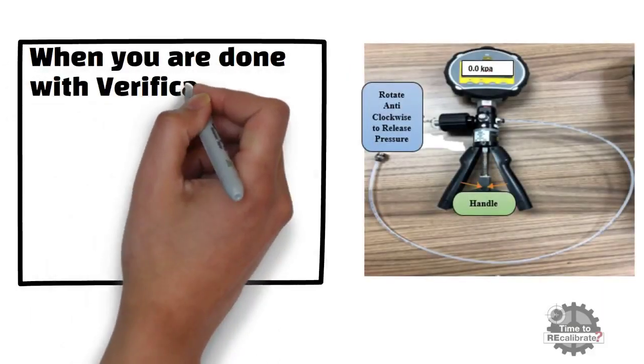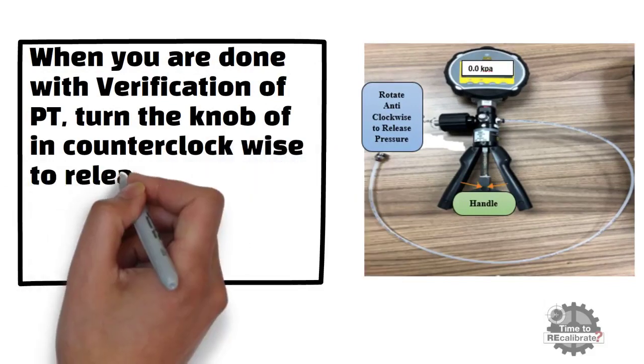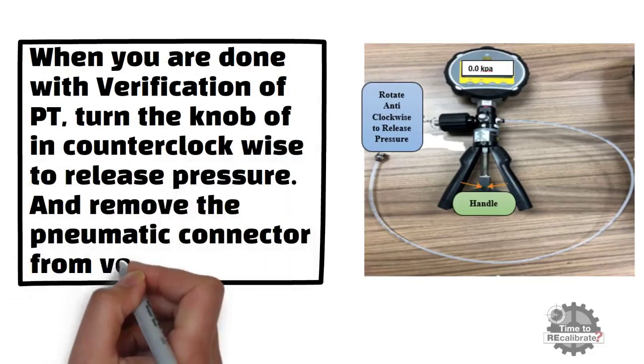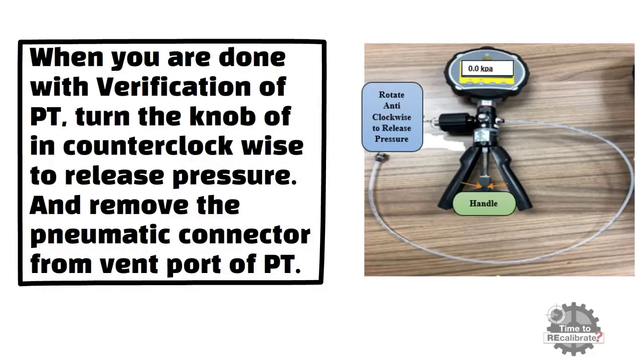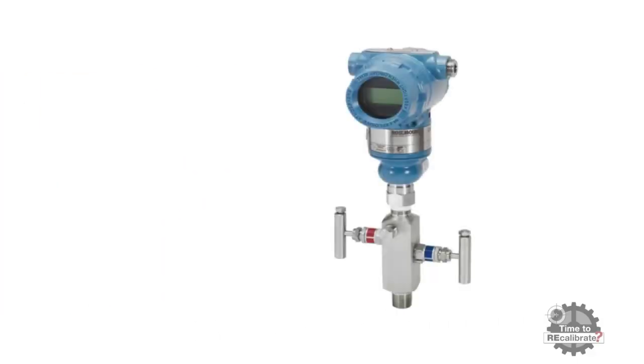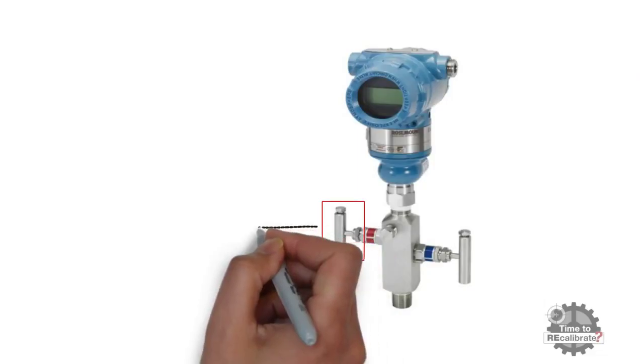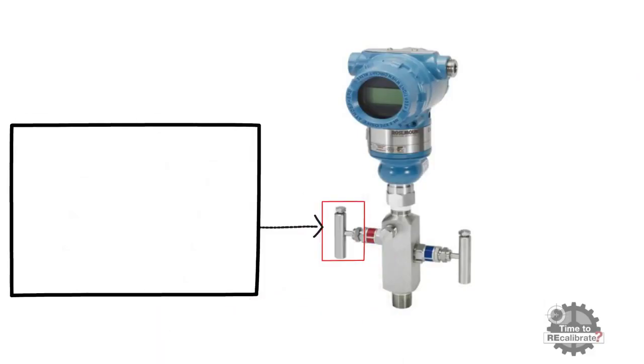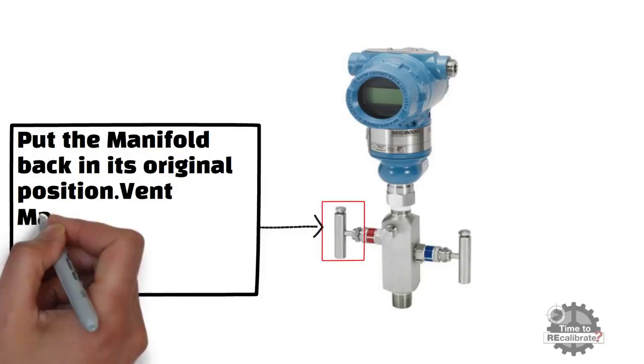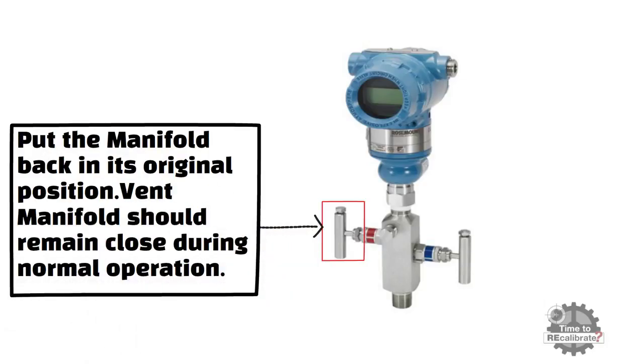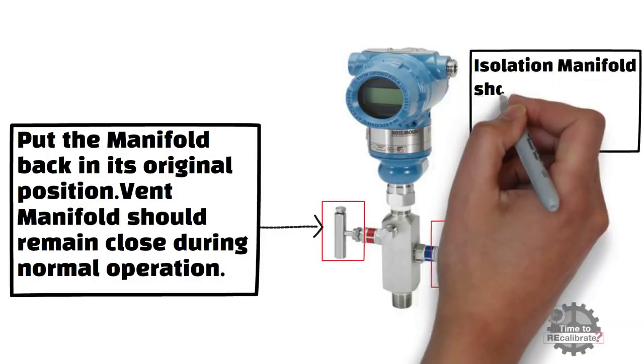When you finish verification of pressure transmitter, turn the little knob of pressure calibrator in anticlockwise in order to release pressure. And remove the 1/4 inch connector from the vent port of pressure transmitter. Close the vent port of pressure transmitter by using the original fitting of pressure transmitter. Now, put the manifolds back in their original position. Vent manifold should remain closed during normal operation. Isolation manifold should remain open during normal operation.